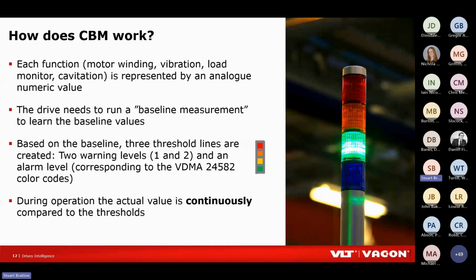The key thing is that once you've set it up and enabled, whether you want it to take an alarm or just generate a warning, the drive is now continuously monitoring this. So you haven't got some guy coming into your facility once a month or once a quarter, going around connecting up his vibration monitoring equipment and taking readings and just telling you on the day whether there's a problem or not. The drive is monitoring this 24/7.